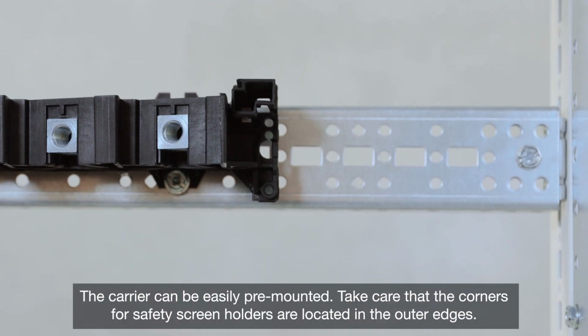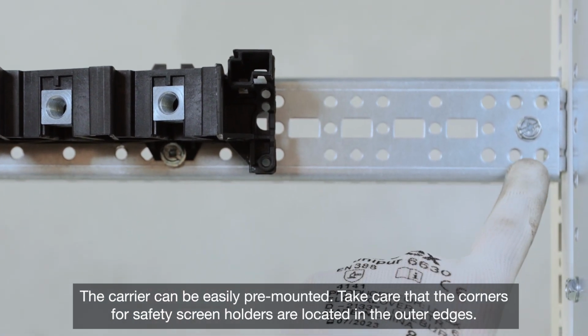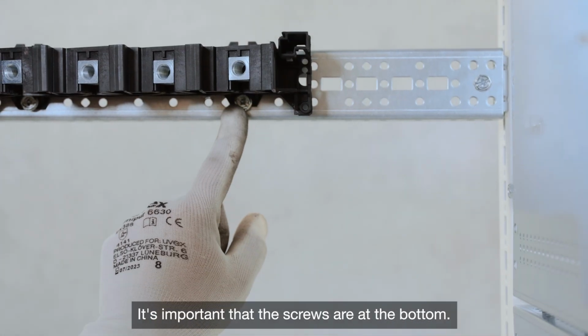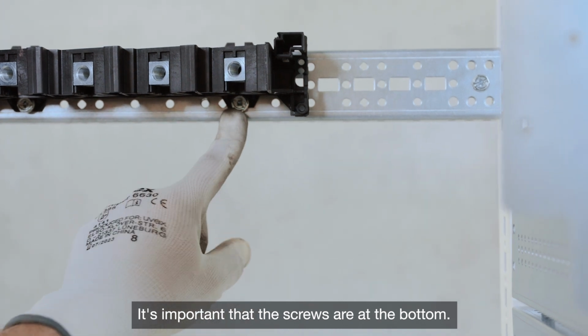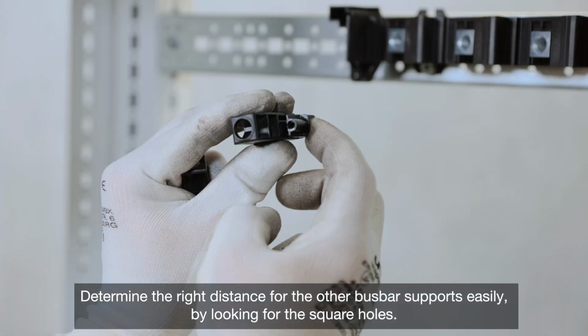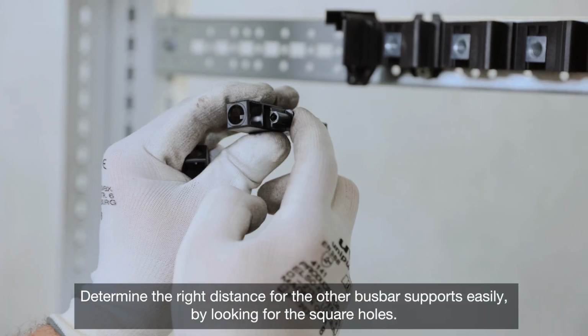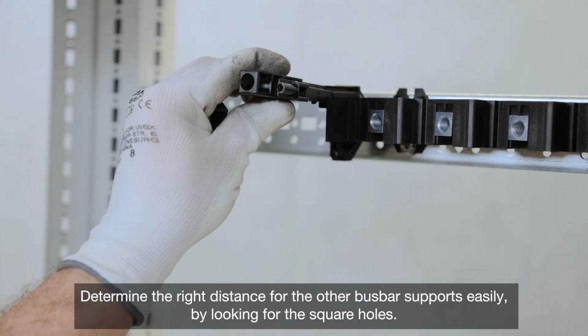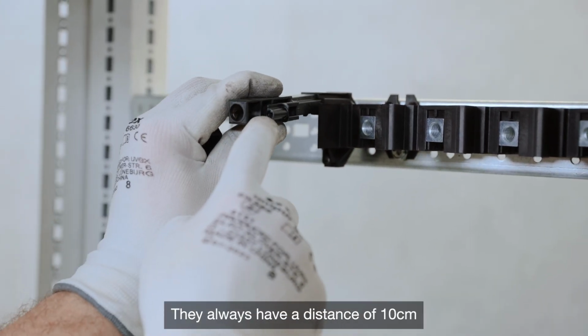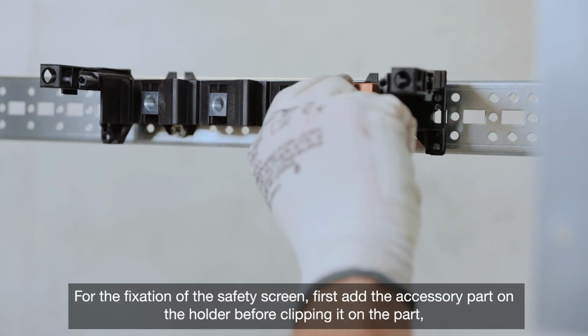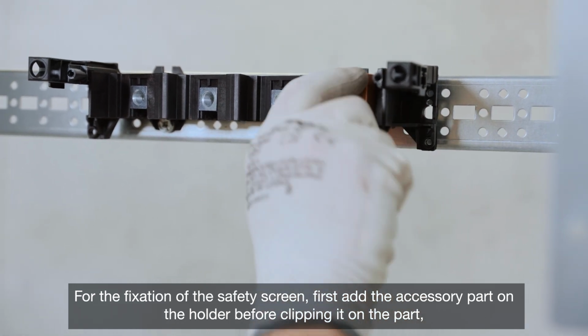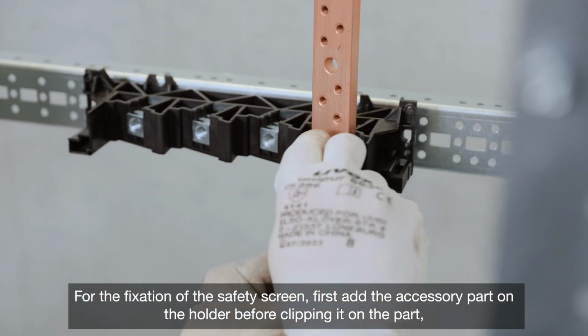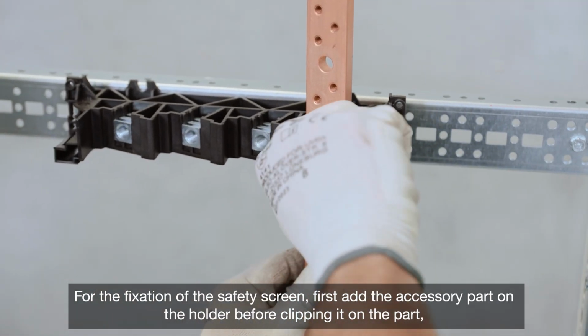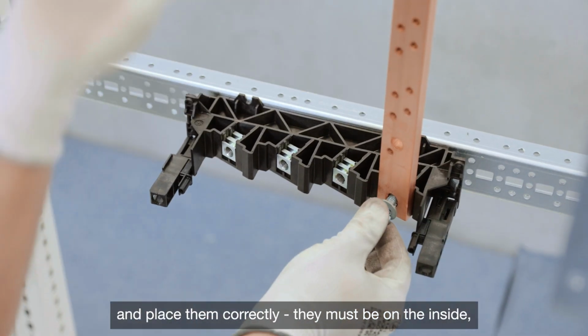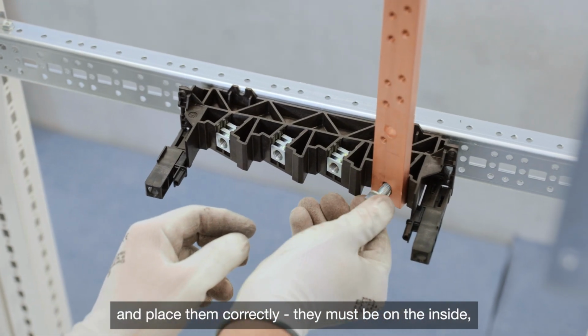Take care that the corners for safety screen holders are located in the outer edges. It's important that the screws are at the bottom. Determine the right distance for the other busbar supports easily, by looking for the square holes. They always have a distance of 10 centimeters. For the fixation of the safety screen, first add the accessory part on the holder before clipping it on the part. And place them correctly, they must be on the inside.